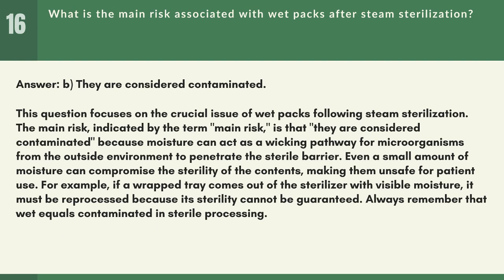Answer: B. They are considered contaminated. This question focuses on the crucial issue of wet packs following steam sterilization. The main risk, indicated by the term main risk, is that they are considered contaminated because moisture can act as a wicking pathway for microorganisms from the outside environment to penetrate the sterile barrier.